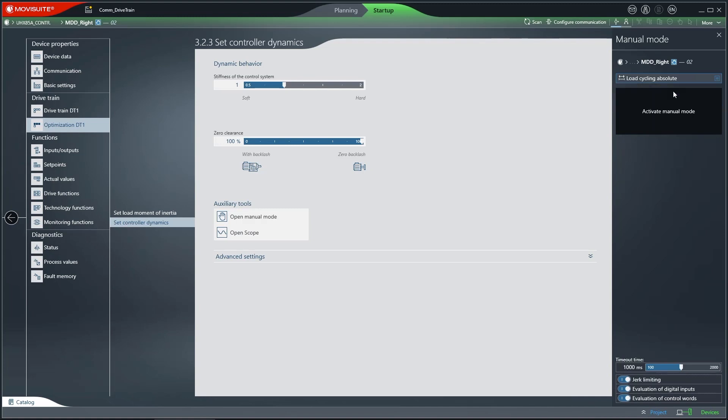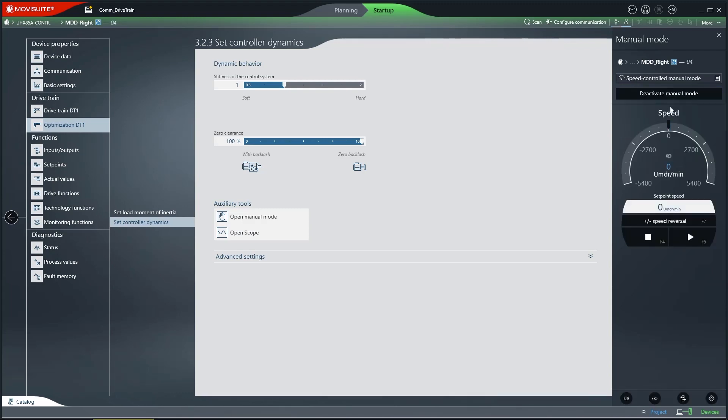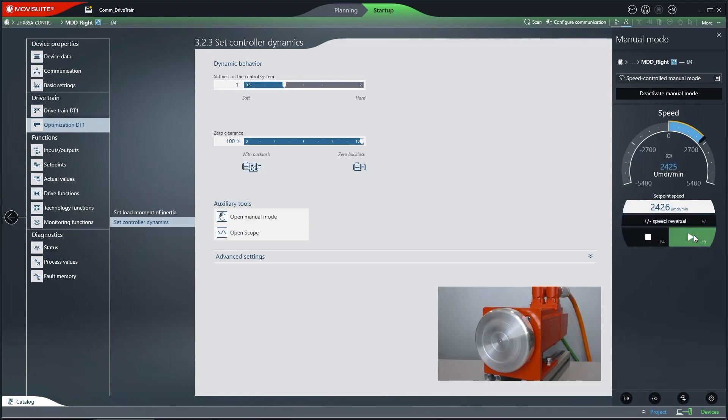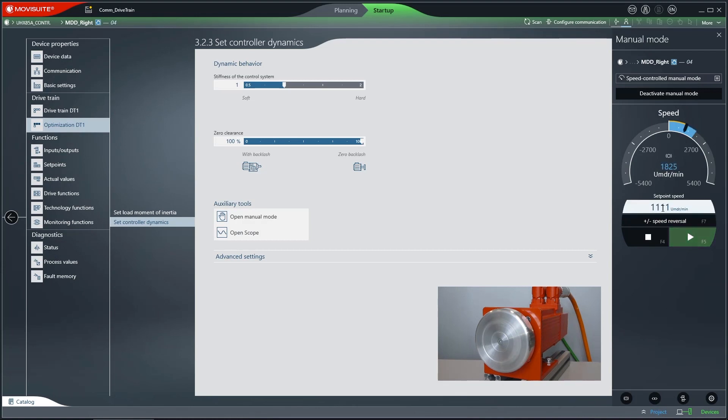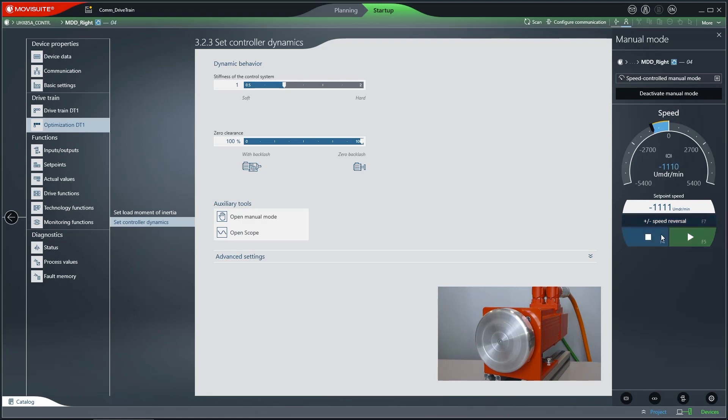A constant velocity control is provided to the inverter in Speed Controlled Manual Mode. You can start or stop the motion using the Start and Stop buttons. The actual speed is displayed in blue. You can enter the Setpoint speed using your keyboard or mouse. And a Speed Reversal is also carried out. All values can be changed when stationary or during operation.